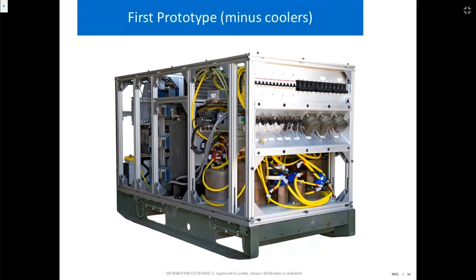There are also 2 signal interface cables, a bit hidden underneath the middle battery connectors, that go to the TQGs. We installed remote start kits on the TQGs, giving feedback on status, alarming, and contactor status, so the cube needs awareness of that TQG's status, hence those signal cables. That's really the main external interface to this system.